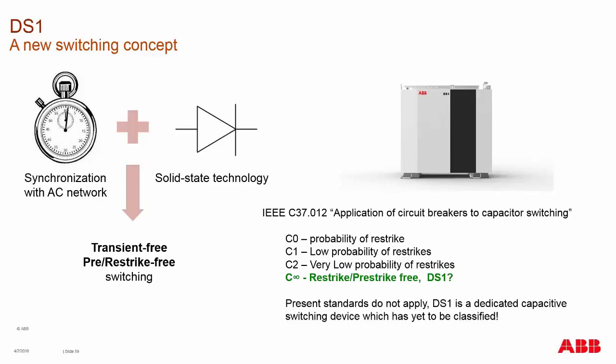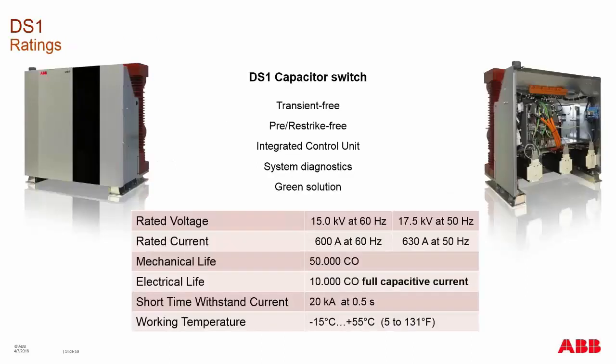The DS-1 is labeled C infinity — not an official rating — but as a new-to-market device there is presently no standard that fully applies to its ability, so we would label it a C∞ device. We have it rated for both IEC and ANSI markets: ANSI at 15 kV, IEC at 17.5 kV. The ratings are 600 and 630 amps with a mechanical life of 50,000 operations and electrical life of 10,000 full capacitive current switching operations. This is a switching device, not a breaker, so it needs circuit breaker or fuse protection in series with it.